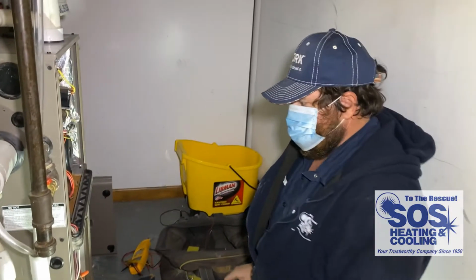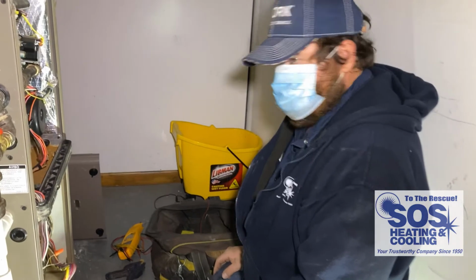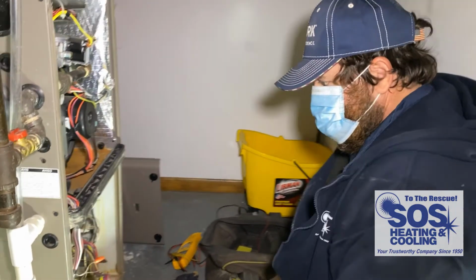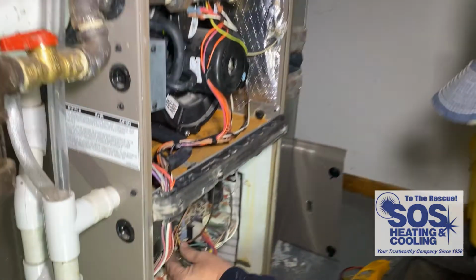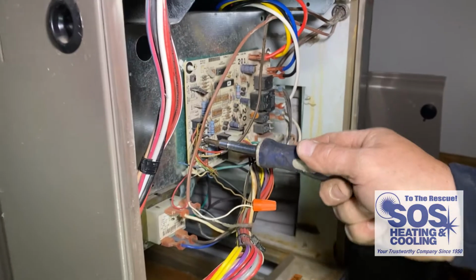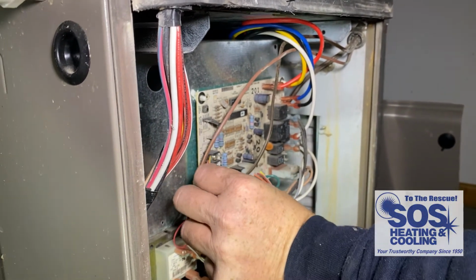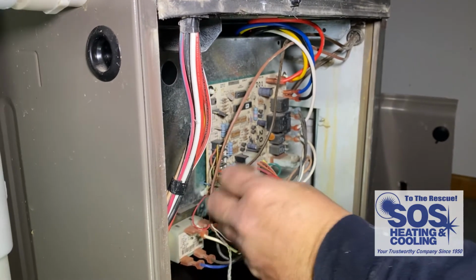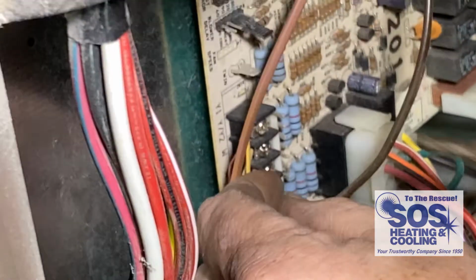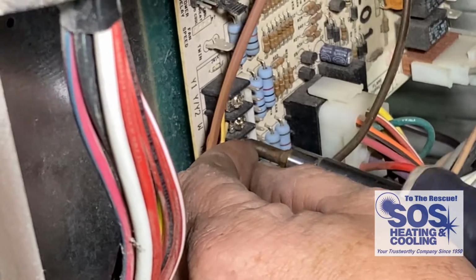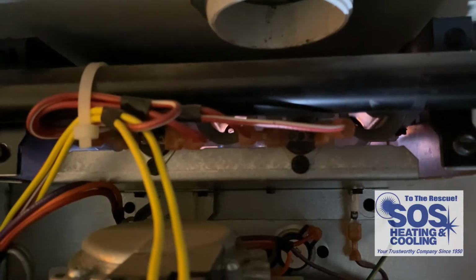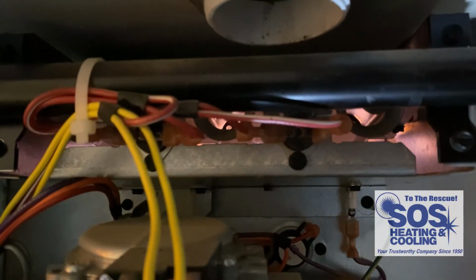I got the motor put in. I put a new run capacitor in. I have the wires wired up. What I want to do is clear out my fault codes. So I'm going to undo the R again, take the call off, power it up, put this wire back on here. We're going to start this guy up. We're going to check some amp draws.